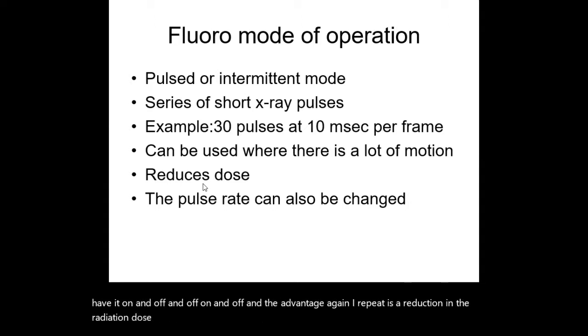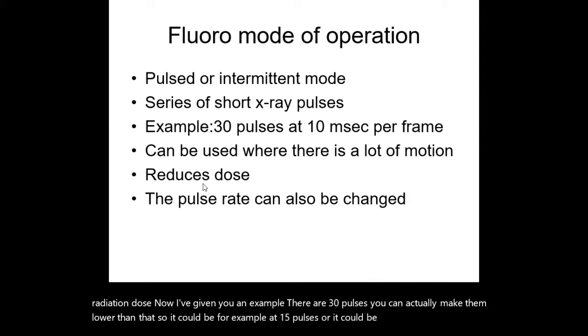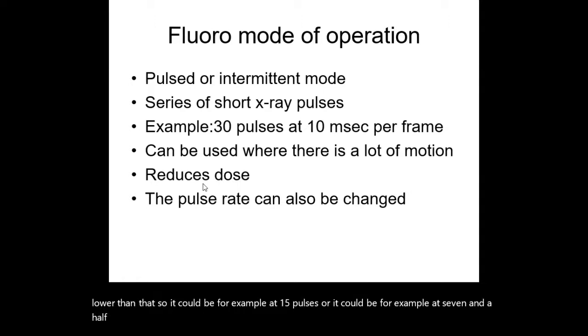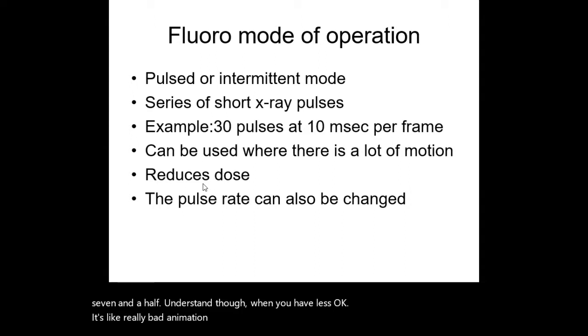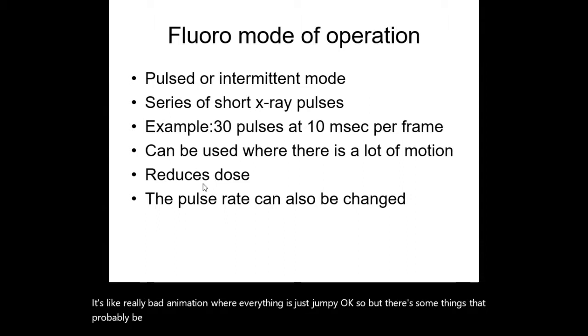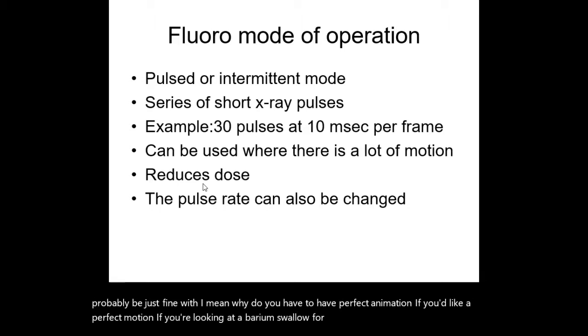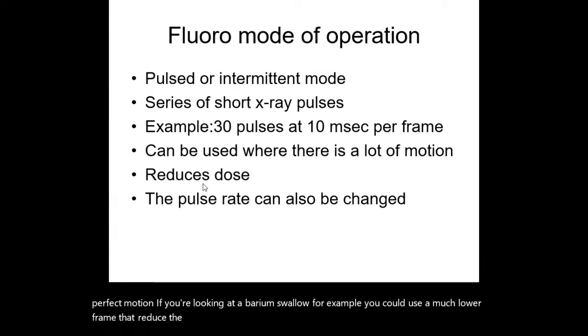Now, I've given you an example there of 30 pulses. You can actually make them lower than that. So it could be, for example, 15 pulses, or it could be 7.5. Understand, though, when you have less, it's like really bad animation where everything is just jumpy. But there are some things you'd probably be just fine with. I mean, why do you have to have perfect animation, or perfect motion, if you're looking at a barium swallow, for example? You could use a much lower frame rate with that and reduce the radiation dose.